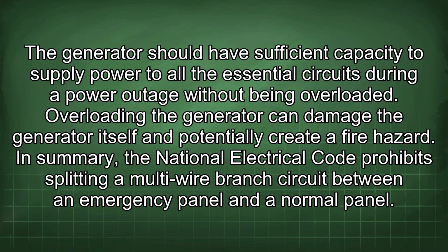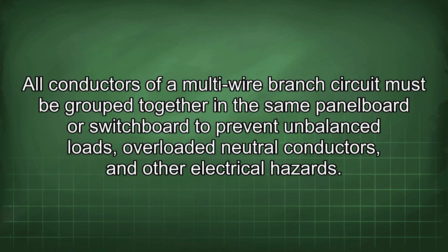In summary, the National Electrical Code prohibits splitting a multi-wire branch circuit between an emergency panel and a normal panel. All conductors of a multi-wire branch circuit must be grouped together in the same panel board or switchboard to prevent unbalanced loads, overloaded neutral conductors, and other electrical hazards.